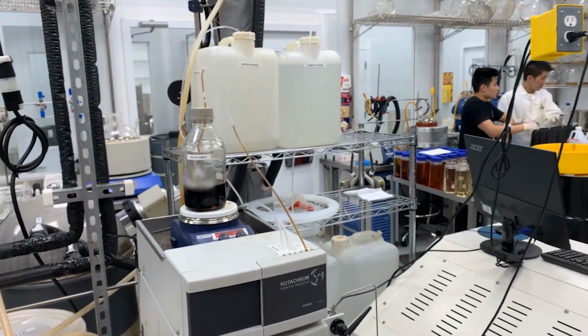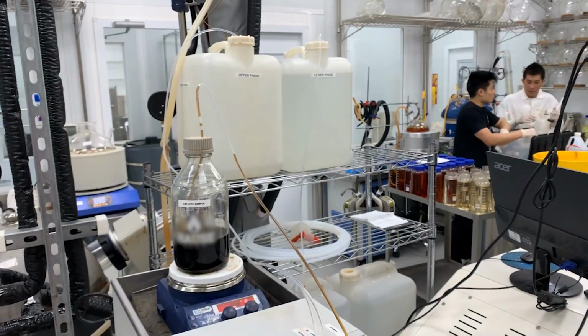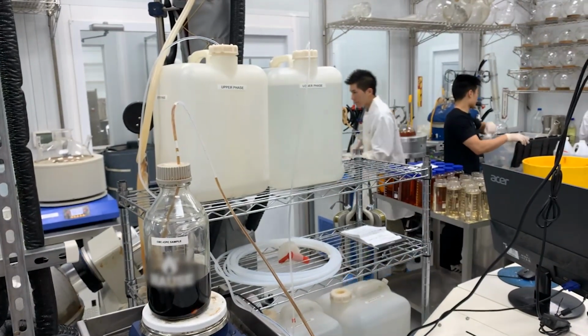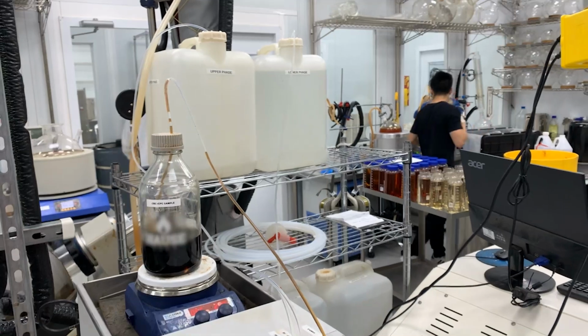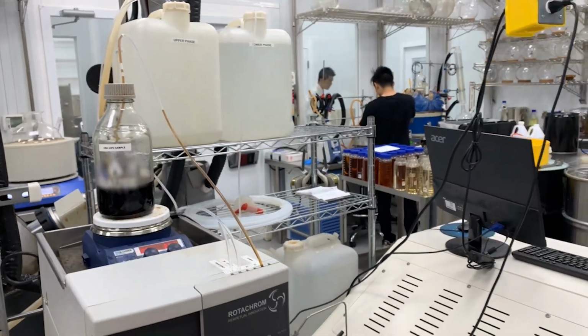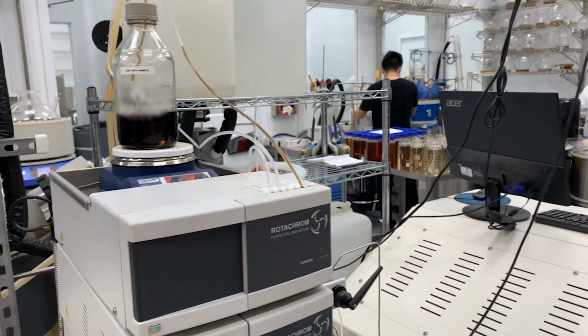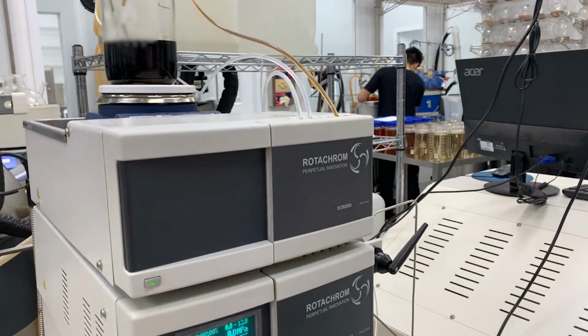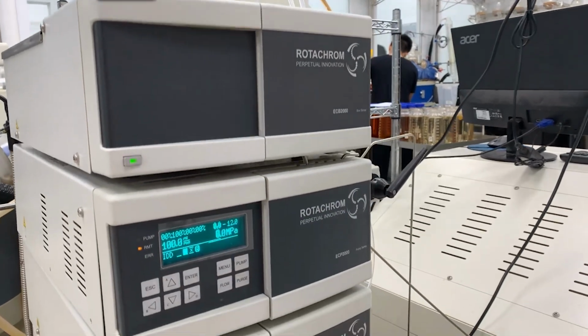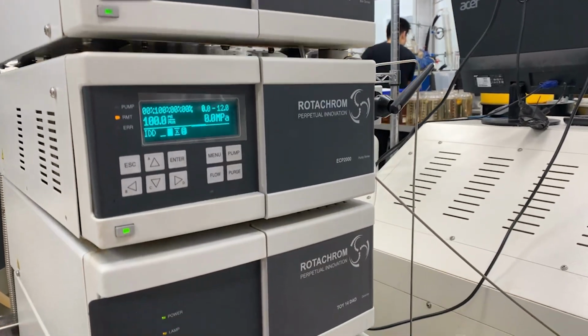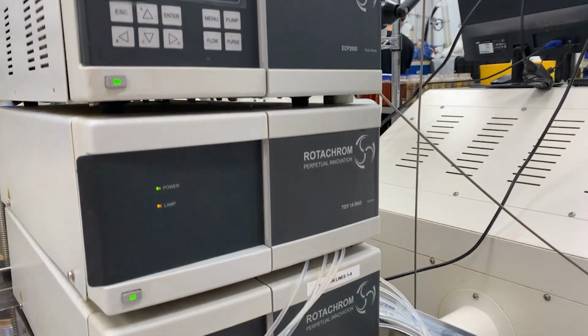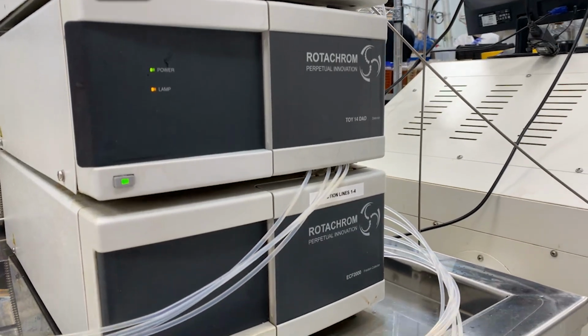In terms of setting the space up, it is a standard lab environment where we need to have the temperature that keeps the operations consistent. People underestimate the importance of temperature variation. If the room starts at 68 Fahrenheit in the morning and finishes at 78 in the evening, the chromatograms will shift. We recommend standard air conditioning in this room.